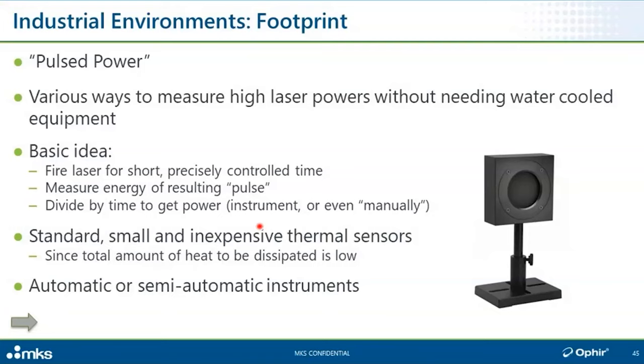Now, we can do that manually. That's kind of trivial, but we can make it a lot easier by having the instrument do it semi-automatically, by asking the user to manually enter the pulse width, or exposure time, and then it'll do the rest. Or fully automatically, if the instrument needs to be fully automatic, and we can equip the device with a fast photodiode to measure the exposure time, and then the user doesn't even need to do that. So I just want to show you what I mean by semi-automatically.